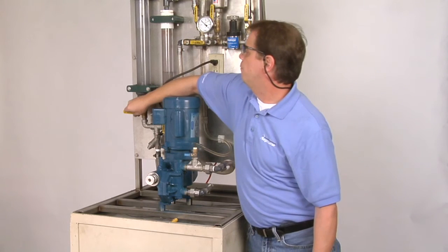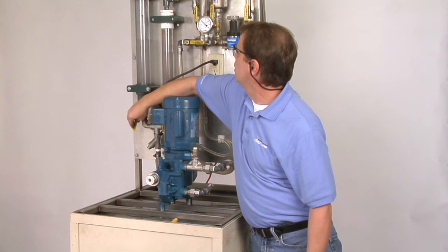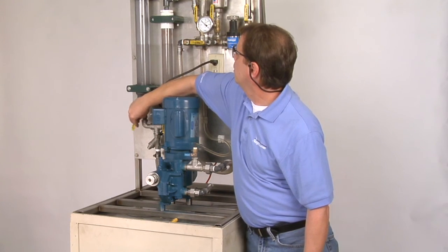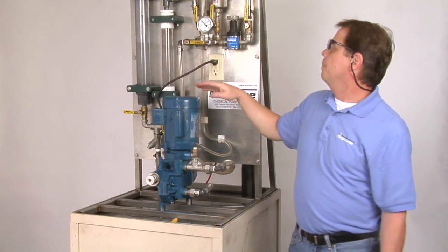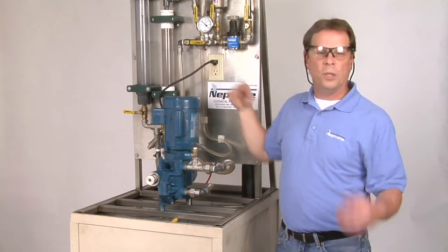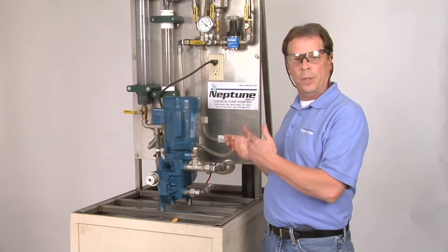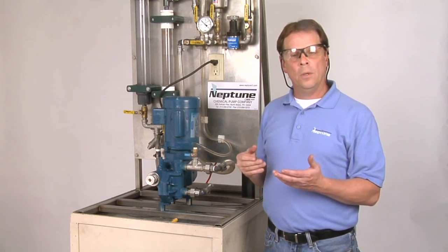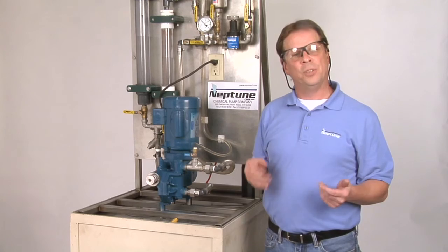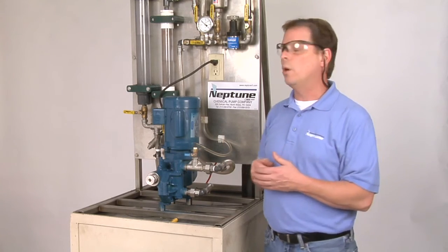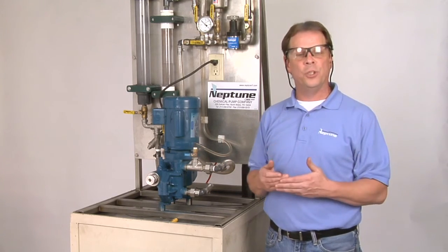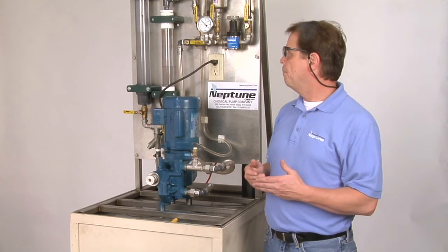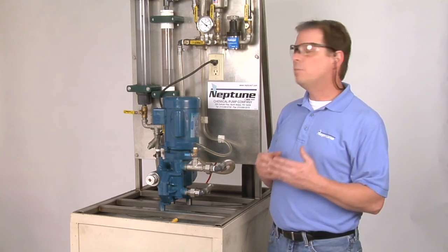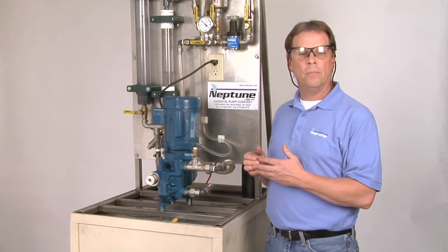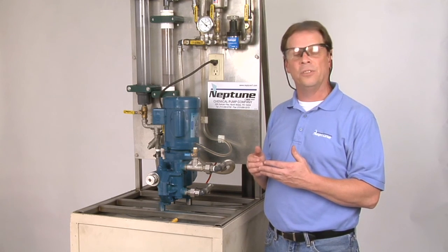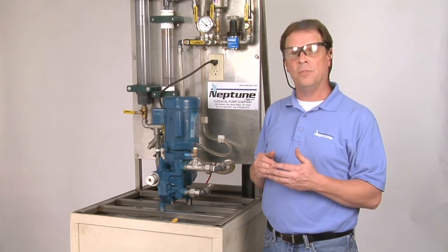Now I'm going to put a little bit more fluid in here. And just let it pump. Now this is a drawdown tube. You can do a test on it to make sure that the pump is pumping at full flow. But I like to let the pump run at 100% for 15, 20 minutes. Make sure that everything is good to go. And that's basically how you would start up a 500 series, 600 series, 6000 series, and 560 series pump.